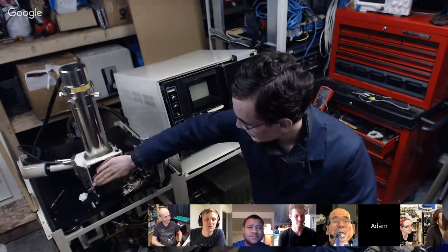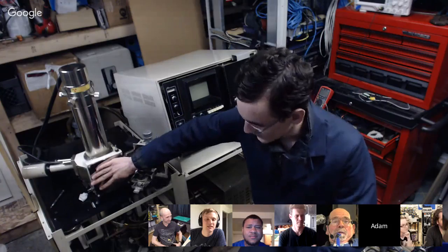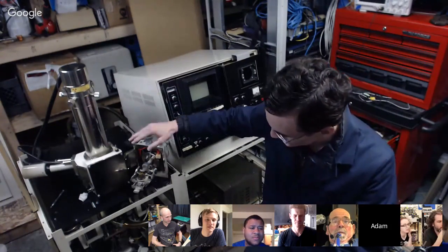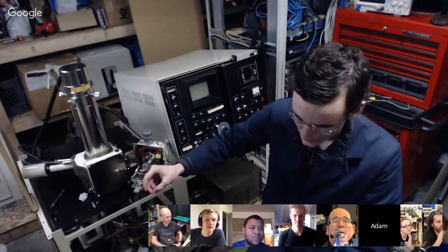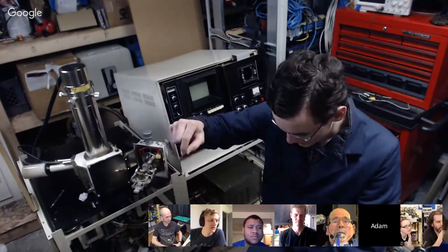So I've installed my blank. I have a blank, basically just a steel plate I can put over this thing. Installed that and got the scope back online. Oh, I had a question: so what you decided to do is just have a non-spinning one, and it's just going to be stationary as you do your testing? Yeah, as I do testing, I really do need it though, because you have to position the sample under the electron beam. You can't move the beam around. You can only zoom the beam in.